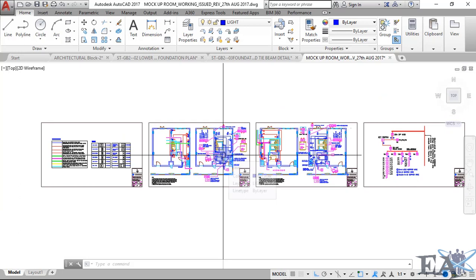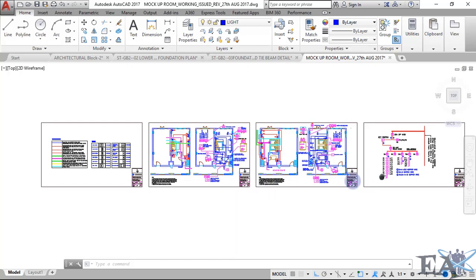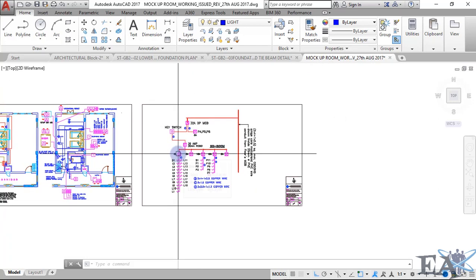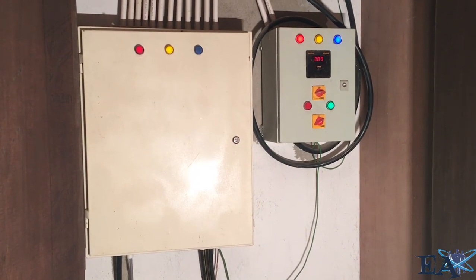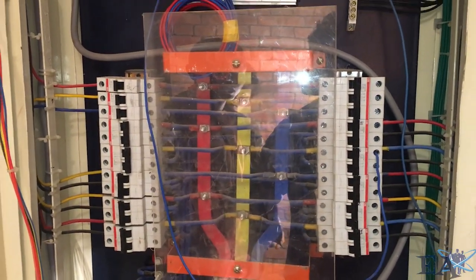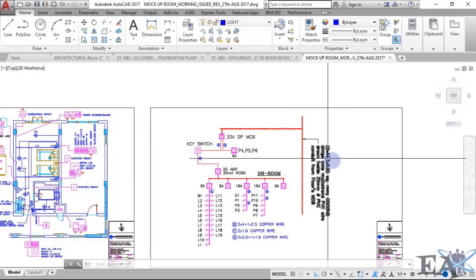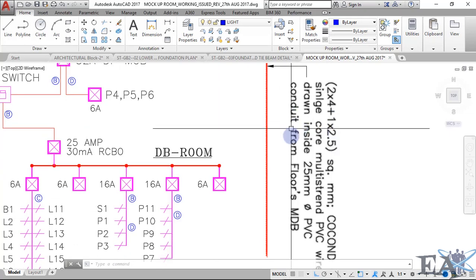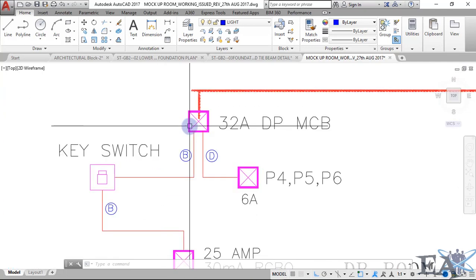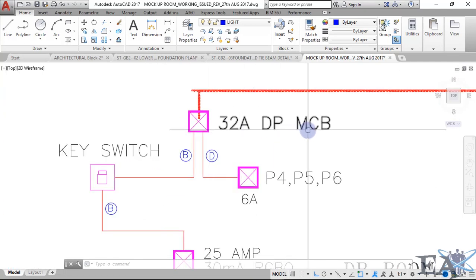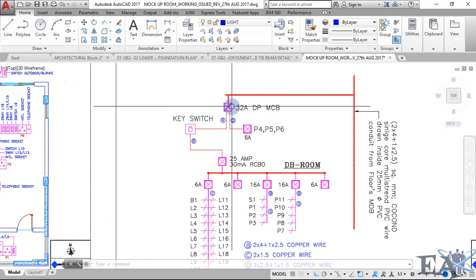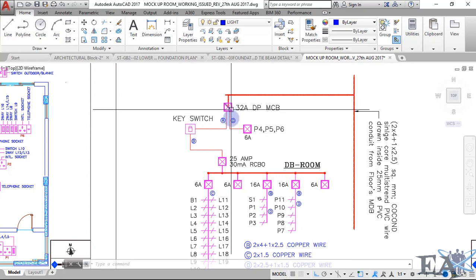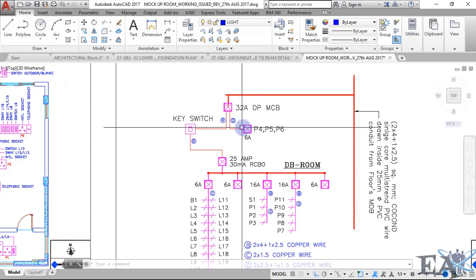This is the wiring of the room. To know the size of the wire and how electrical components are grouped, you go to the DB drawing — DB means distribution box. The main cable enters your building into a main distribution box, from there wires go into different rooms, and each room has its own distribution box. You can see the wire sizes — from the floor's main DB it goes into the room DB, which will have a 32-ampere double pole MCB with a neutral and one phase wire.